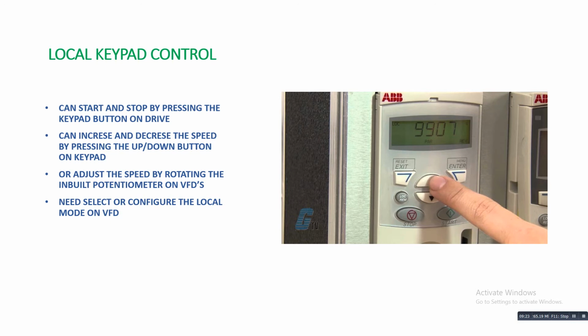So local keypad control. If you want to control from the local keypad, you can start and stop by pressing the buttons on the drive. On each drive you can see the start button and stop button. You can stop the VFDs by pressing these buttons. Some VFDs have the local remote selection on the keypad itself. Some VFDs you have to enter the configuration level and select the local remote settings. Then for increasing the speed you can use the up down buttons, and you can decrease and increase the speeds.